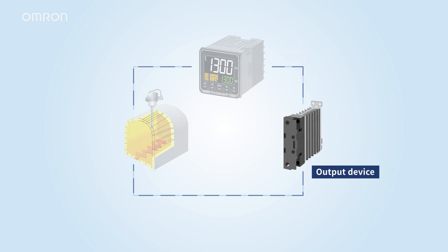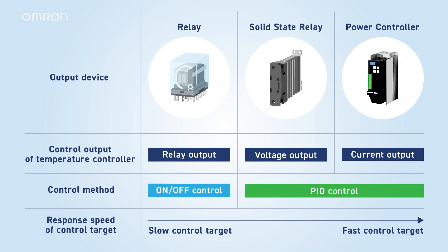Next, let's introduce the types of output devices. The main output devices include relays, solid-state relays, and power controllers. These devices receive control output from the temperature controller to turn the heater's power on and off. Output devices are primarily selected based on the response speed and control method of the target being controlled.